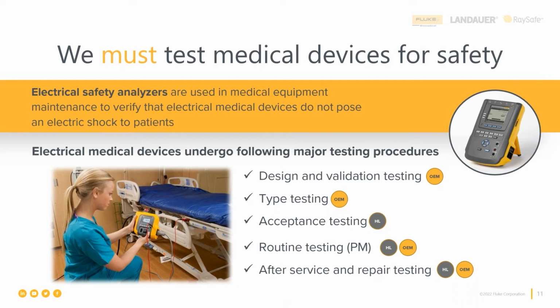Aside from that, for the hospital, we have acceptance testing, and there's two scenarios there. The first one is when a medical device is brand new and comes into us before we put it into clinical use, we need to do electrical safety measurements during that time period also, and then certainly once per year in our routine testing. But the second acceptance testing scenario is if we send a medical device away from our hospital or client facility for someone else to repair, when it comes back in, we need to do another acceptance test that includes measurements for electrical safety just to verify it's safe and effective for clinical use. And then certainly after any repair that we do ourselves in-house, we need to perform electrical safety testing again before we put that medical device back into clinical use.